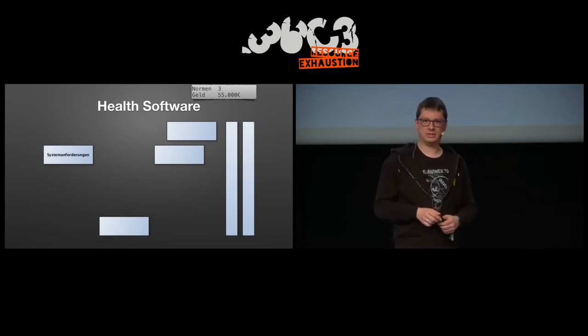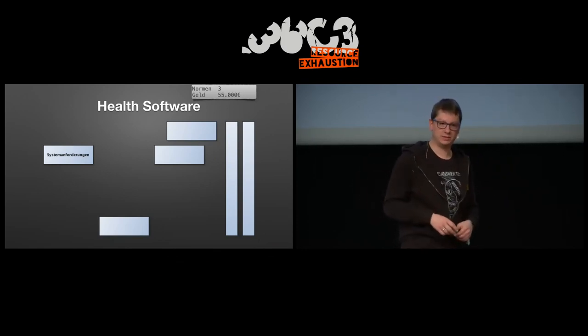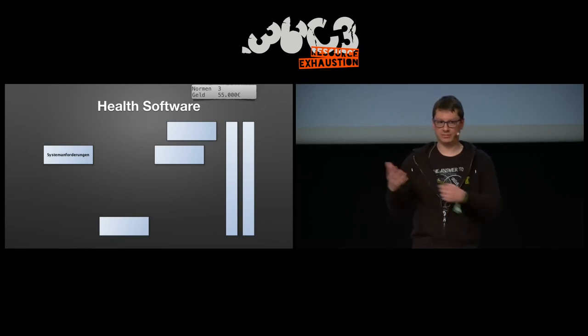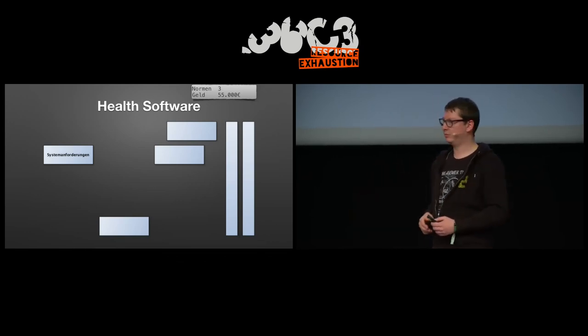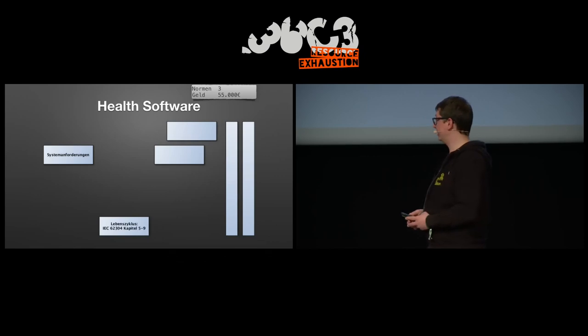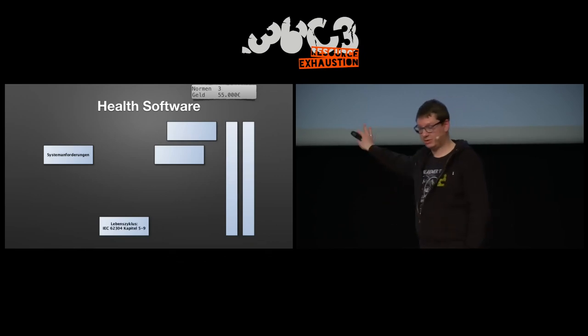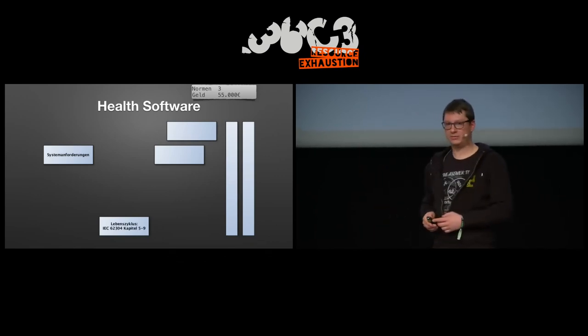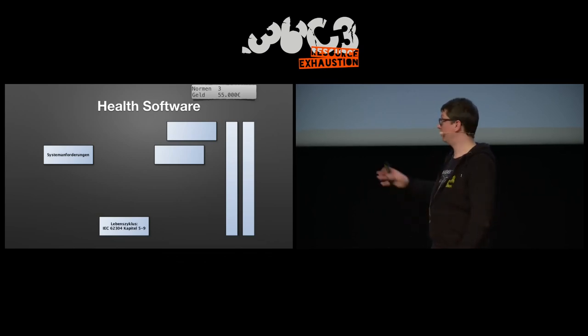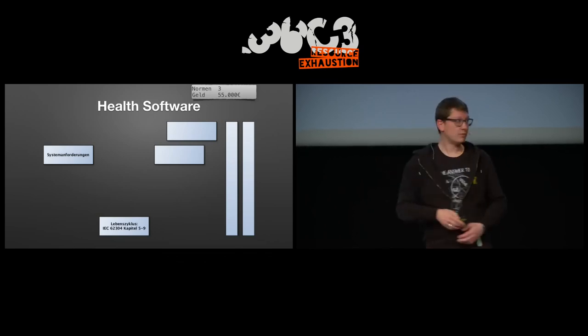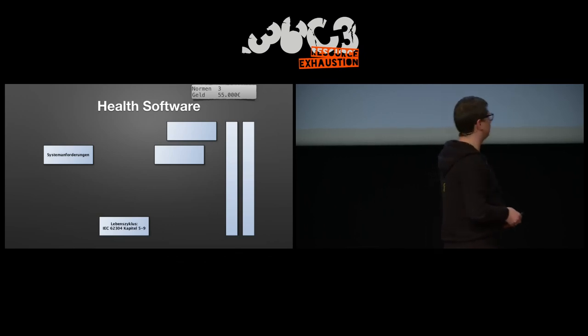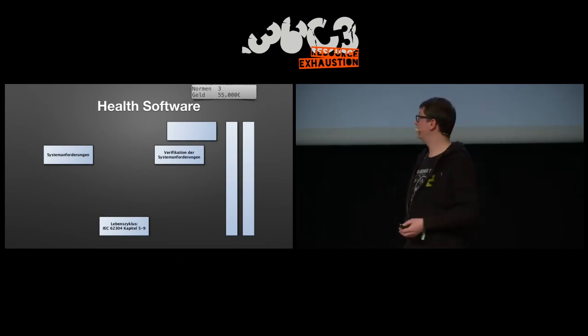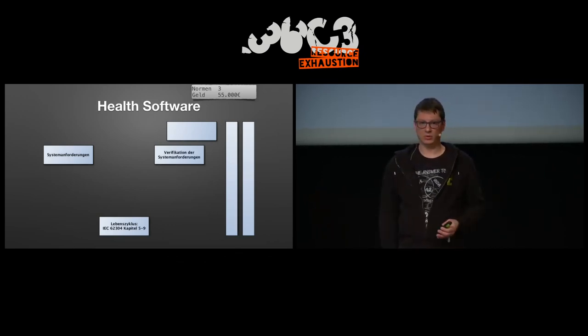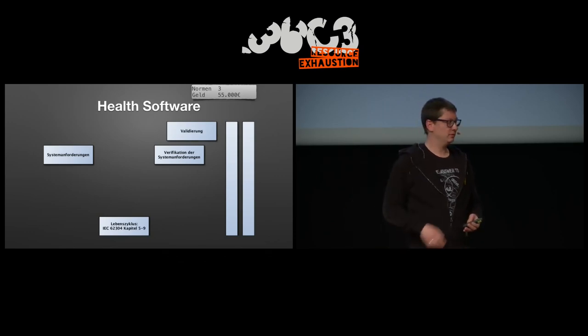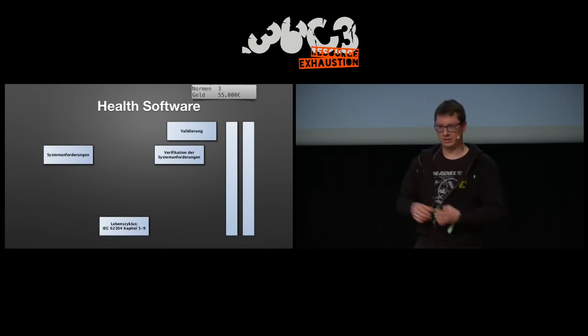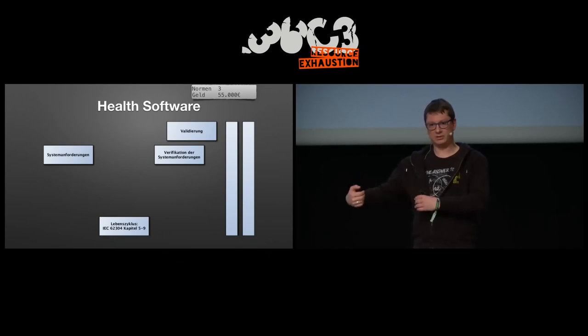So now you say you've done everything for software, nice, but don't ignore the whole environment where the software will live. So you have the system requirements. Then the next step is the life cycle, determined in the IEC 62304. Then you have to verify the system requirement, and on top of that you have the validation.